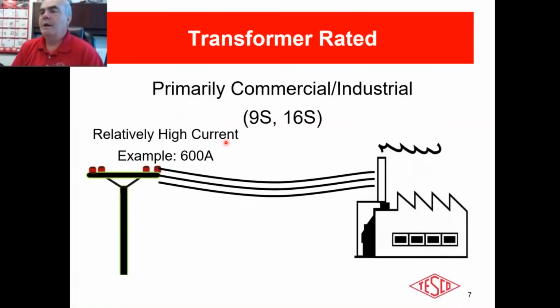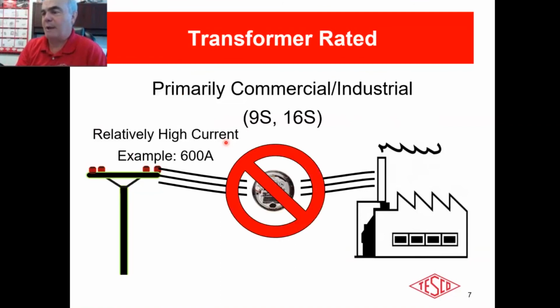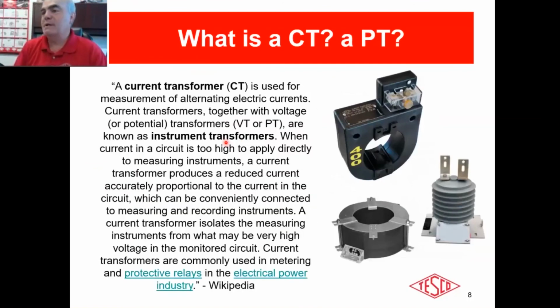All right. Now, what's the difference? Transformer rated, 9S, for example, we got 600 amps going into the factory here. You can't put the meter right in line because the meter is not designed to handle 600 amps. All right. So what we use is we use CTs, and sometimes we also use PTs. So what exactly is a CT? We call them CTs, current transformers. They are actually a type of instrument transformer.